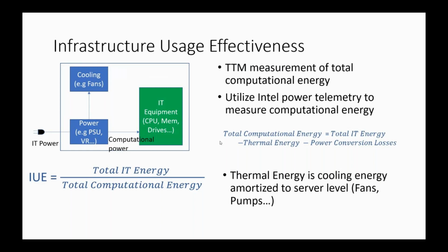And then you have local cooling, maybe fans typically. Today on a given server, the fans are about 10% of your server load. So if you take this at a server level and define a new metric: the incoming power into your server at the wall plug, and the total computational energy that you used up — that ratio tells you the overhead you incur, because it subtracts out the thermal losses and the power conversion losses from the equation.